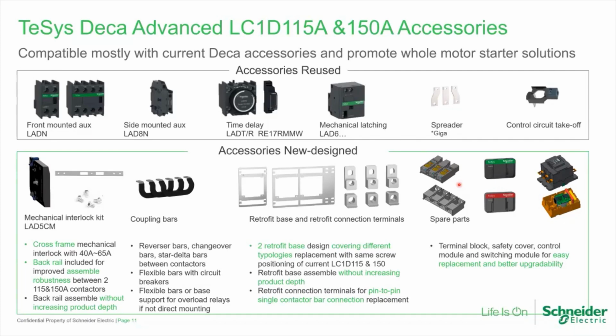We also have safety covers available if you want to use this contactor as a safety contactor. Let me tell you that all the contacts, auxiliary contacts, are safety contacts, and hence you can simply change the cover and use this contactor as a safety contactor. We also have spare switching module and control module, which was not there in the existing contactor. So not only the control module, not only the coil, but the switching module also can be replaced if required.